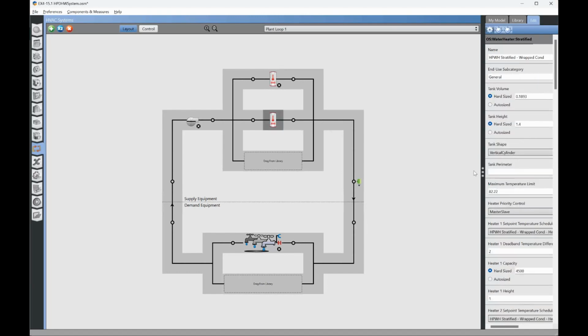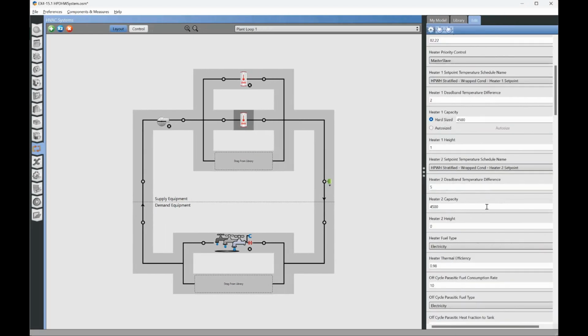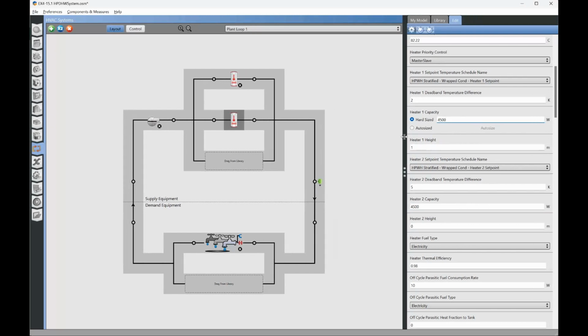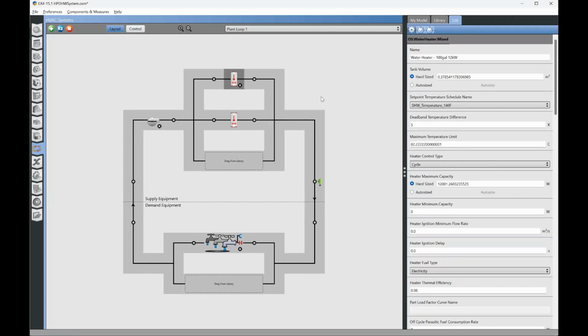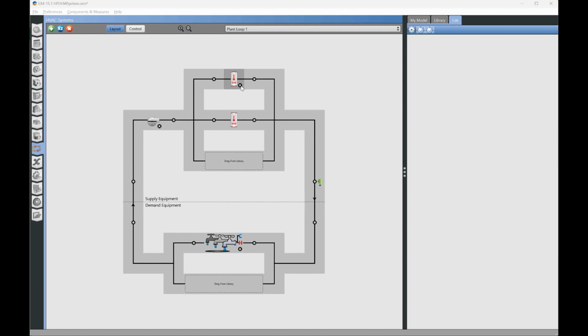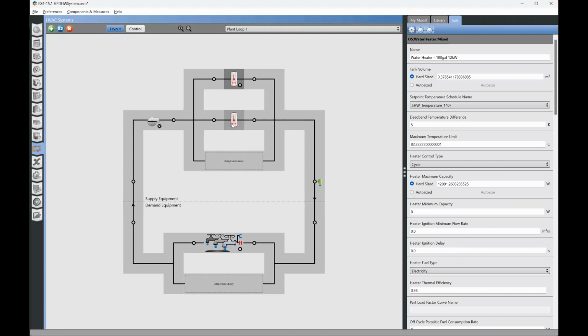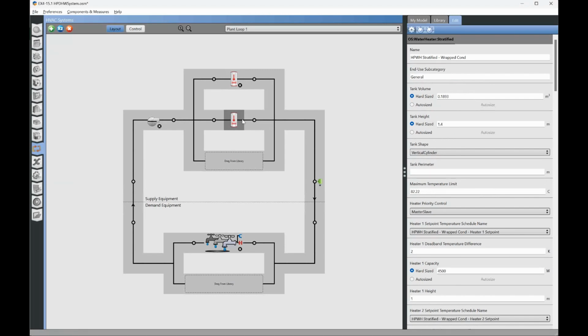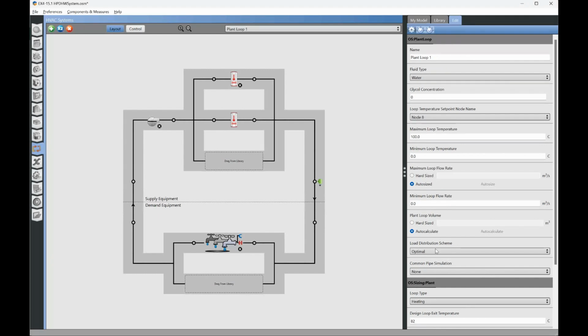This one has, what size heaters does this one have? Okay, this one has a heater 1 of 4.5 kilowatts and another heater 2 of 4.5 kilowatts. So that's only 9 kilowatts. So we would have to update that. But for now, what we can do is just run the model and see how this turns out. So let's do this first. Right now we have the 12 kilowatt heater in first place. The heat pump in second place. We do have a load distribution scheme set for the loop as optimal.